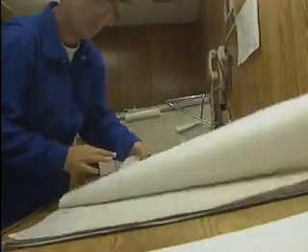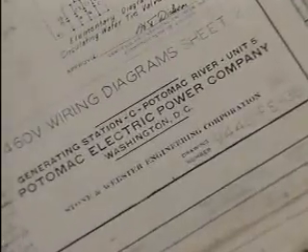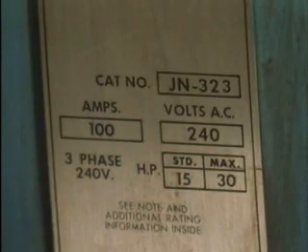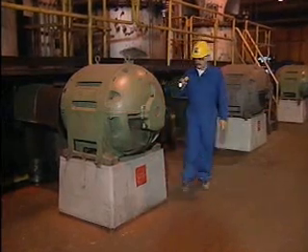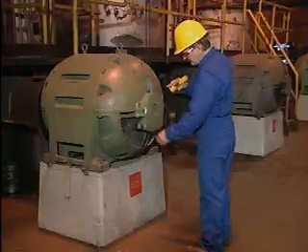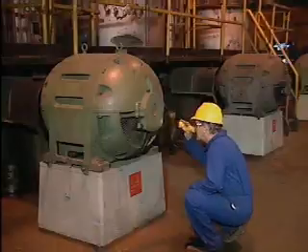Another aspect of performing electrical work safely is determining the nominal or normal operating voltage of a circuit or a piece of equipment. One way to get information about the nominal voltage for a circuit or a piece of equipment is from an electrical diagram. Another way is to read the information on the equipment's nameplate, if one is available. Being able to determine the nominal voltage level of a circuit or a piece of equipment is an important part of working safely because it helps you determine the types of protective gear you'll need.